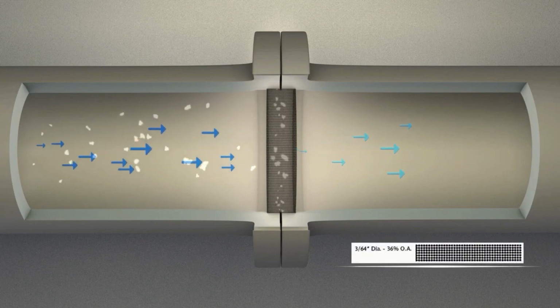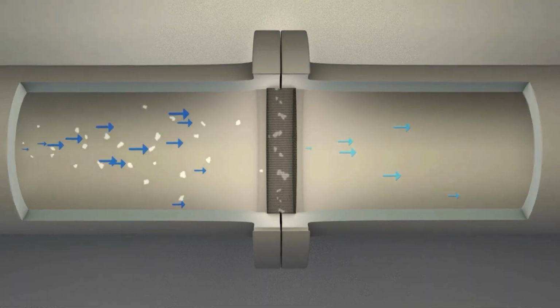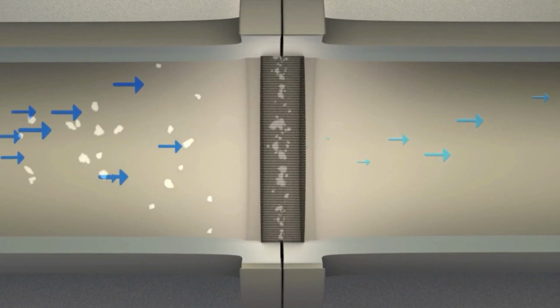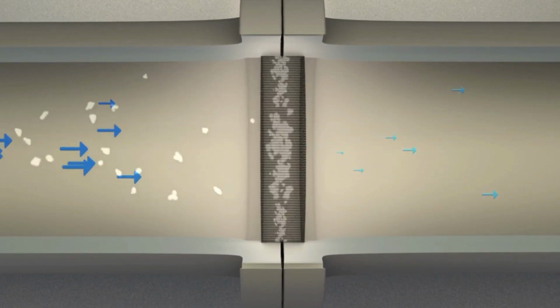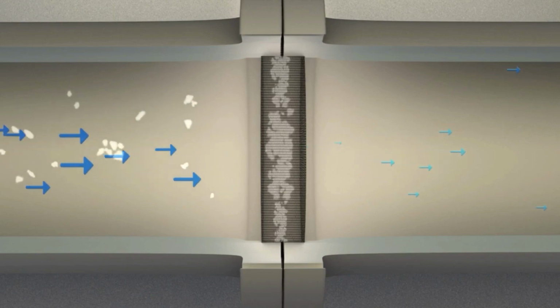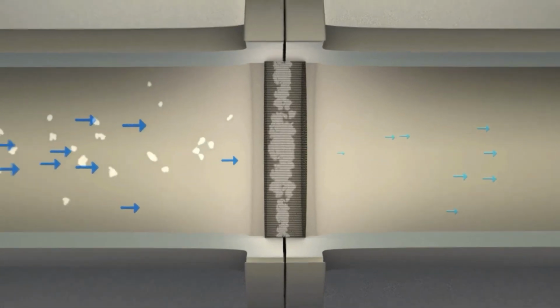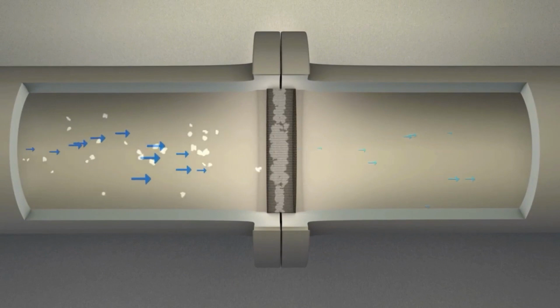The filter will obstruct the flow through the pipe, lowering the pressure on the downstream side. These effects may vary depending on the filter's construction. Filter media is the material that removes impurities. The smaller the pores, the larger the friction. Higher friction means greater pressure drop.